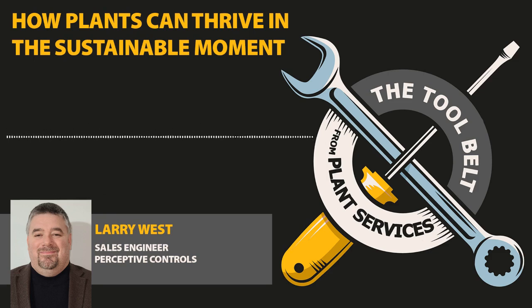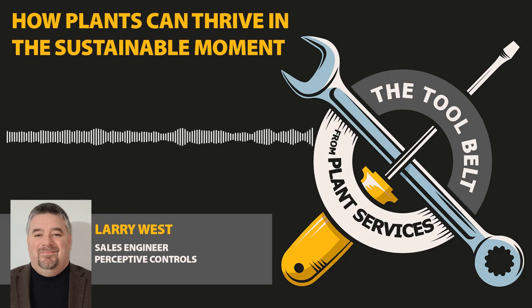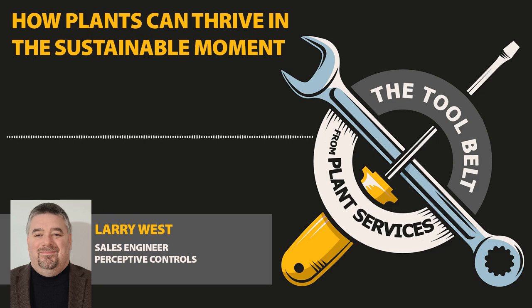If after that you're still concerned, there are other ways to manage SCADA data outside of your network. An IT team can create a guest or separate network over which the data is collected and managed, and then you can bring it over through HTML or other resources to see the data on the computers at your location without affecting, or infecting, if you will, your central network. To take it even a step further, there are many devices and tools that allow you to use cellular services to push signals from one device to another, which completely removes any signals from any of your networks.